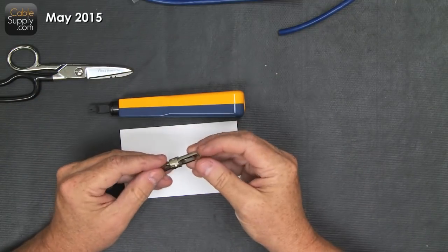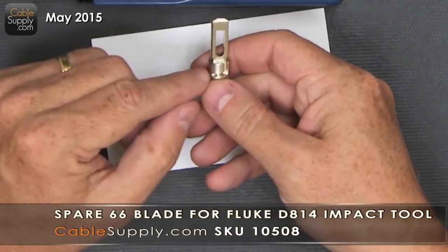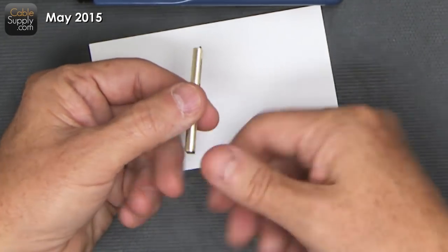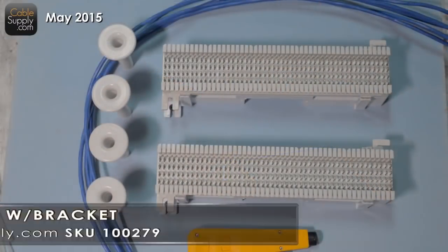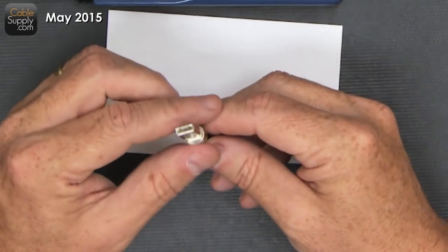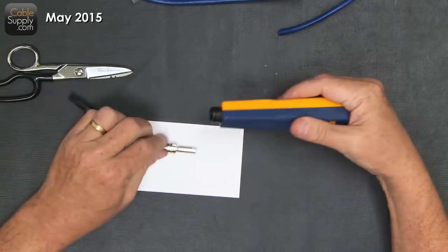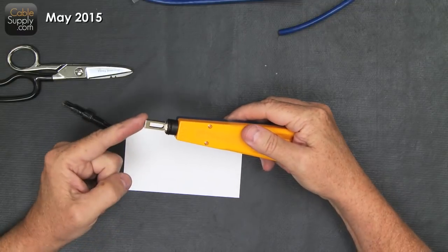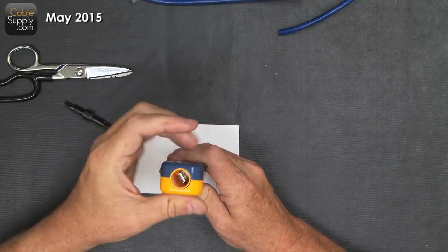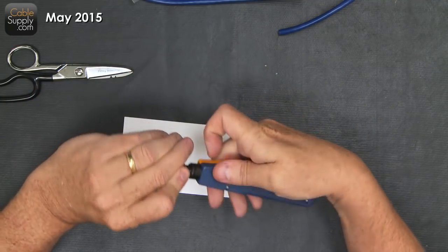This is a 110 blade, mostly used today for computer networks, patch panels, jacks, and all sorts of terminations. You also have a 66 block blade. The 66 blade has a cutting version and one that just pushes the wire into the 66 block without cutting.